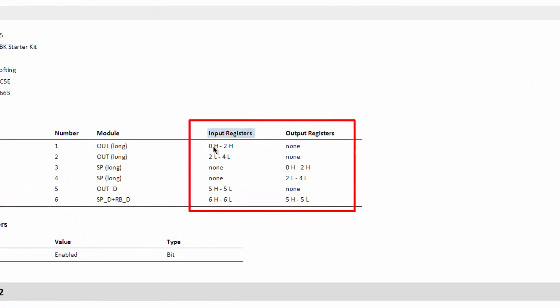Input data is mapped to input registers. Output data is mapped to output registers. The data of the device is stored one by one on the registers. The data of a module can start or end on the high or low byte of a register. This is indicated by H for high and L for low.